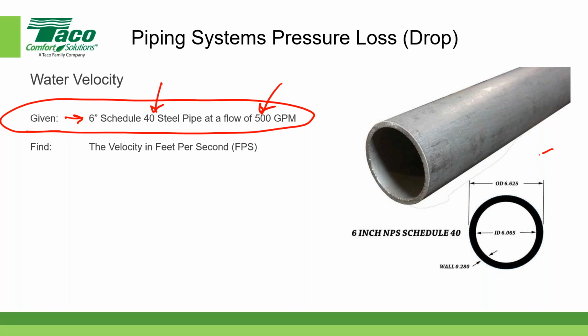And if you'll notice in my little diagram, it says that the outside diameter is 6.625 inches and that the inside diameter for the Schedule 40 pipe is 6.065 inches. And the wall thickness is 0.280 inches. Now, the reason I like to point this out is because if we change the strength of the pipe, it's the inside diameter that gets smaller because the wall thickness gets larger. So the stronger the pipe, the thicker the wall, but the outside diameter remains the same.